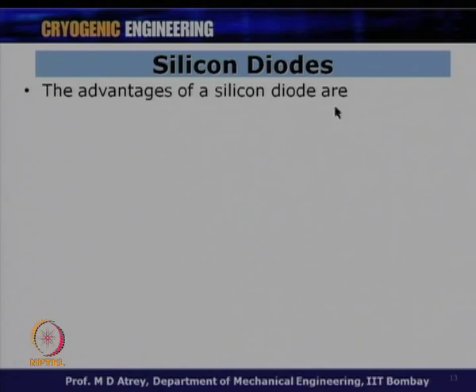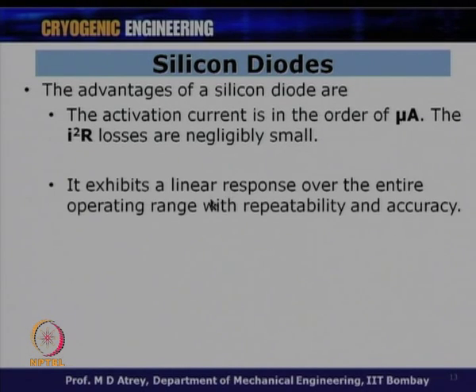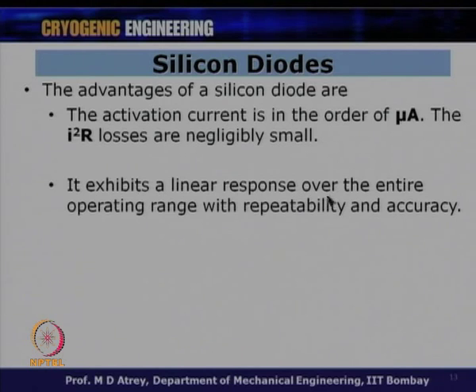The advantages of a silicon diode are that the activation current is in the order of microamps — just 10 microamps — so I²R losses are negligibly small. It exhibits a linear response over the entire operating range with good repeatability and accuracy, which is what is expected from a good sensor.